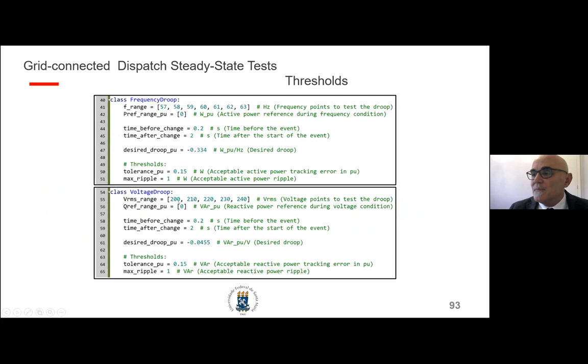So in summary, our primary controllers are considered to pass the frequency support steady state test. In terms of frequency, all have 100% in the tests that we have performed in steady state. The Droop presents a significant error on the volt-var curve among all the primary controllers. We have already identified this using the steady state analysis with small signals, so this was not a surprise, but the test revealed it.